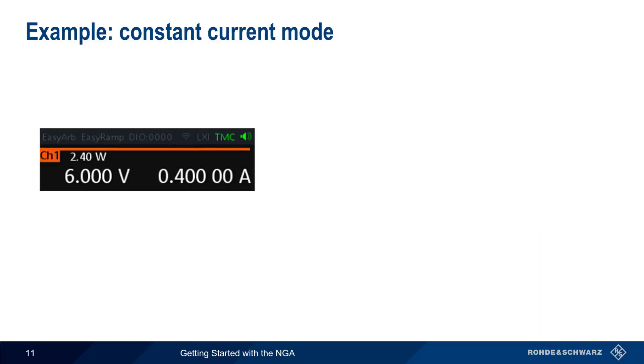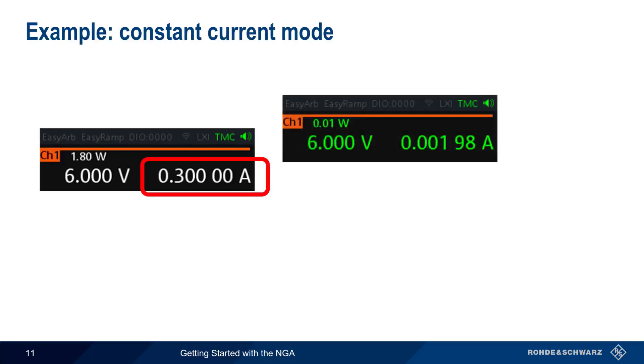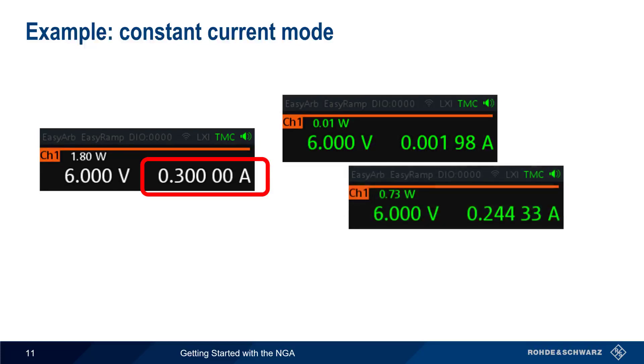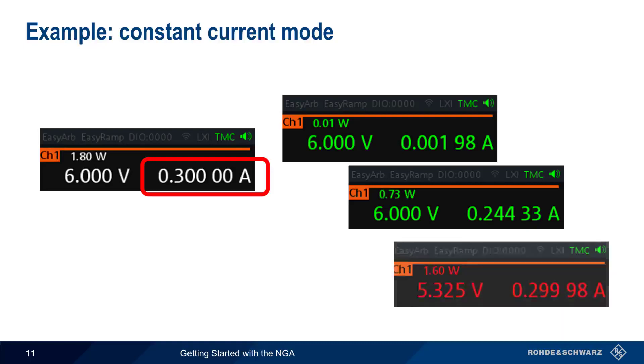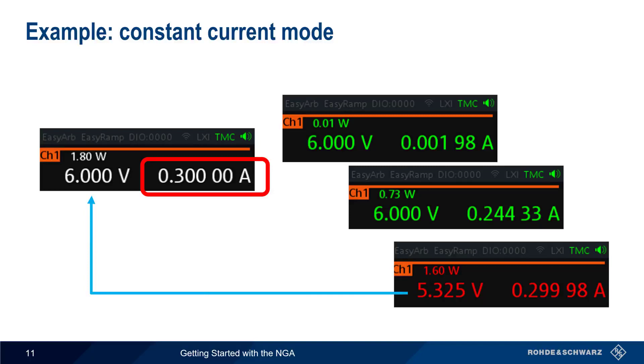Now let's decrease the current value from 400 milliamps to 300 milliamps. The output voltage still starts out at 6 volts and remains constant when output current changes, but only as long as the limit of 300 milliamps is not exceeded. If, however, more than 300 milliamps would be drawn, the NGA automatically switches to constant current mode, lowering the output voltage until the output current does not exceed the configured current limit. When operating in constant current mode, values of power, voltage, and current are displayed in red.